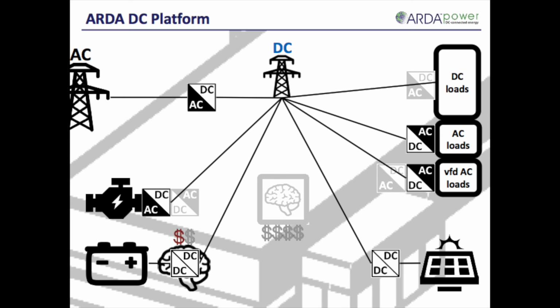Solar and fuel cell energy sources are connected directly to the bus using DC-DC converters, while high-efficiency CHP, microturbine, wind, gas, and diesel gensets can be connected directly to the DC bus. DC loads, like LED lights, are also connected directly to the DC bus. AC loads can be connected to the DC bus via low-cost dedicated DC-AC inverters, or directly to the DC bus in the case of VFD-driven AC loads.